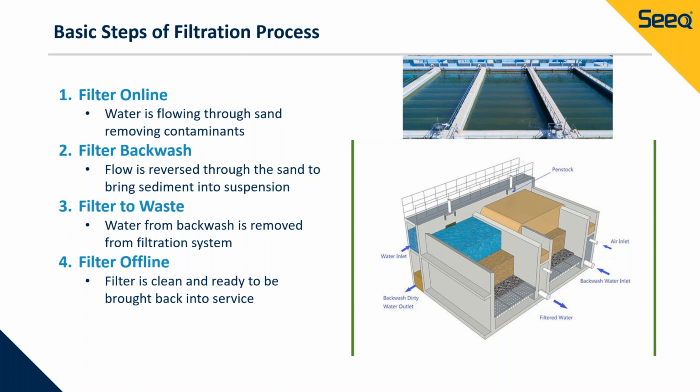So first we have the filter online stage. This is when the filter is actually running, it's in service, water is flowing through the sand to remove contaminants. The contaminants are basically being caught in aggregates.